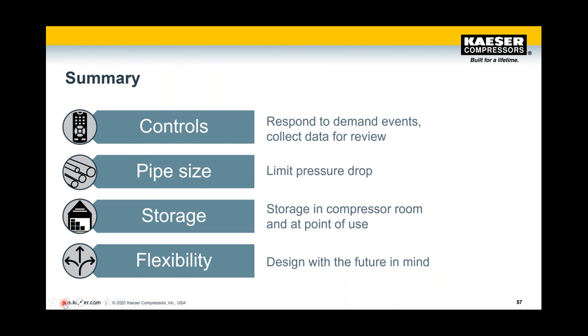In summary: controls — whether individual or master — maintain compressor operations safely and respond to demand events, providing a wealth of information. Piping: limit pressure drop and minimize velocities. Storage in the compressor room provides a control buffer, preserving longevity and delivering energy savings, including permissive starts so you're ready if you lose a compressor. Storage at the point of use eliminates noise back into the system and maintains smooth operation so that production is unaffected. And finally, flexibility — design with the future in mind. Now we'll go back to Kimberly and finish with our Q&A.